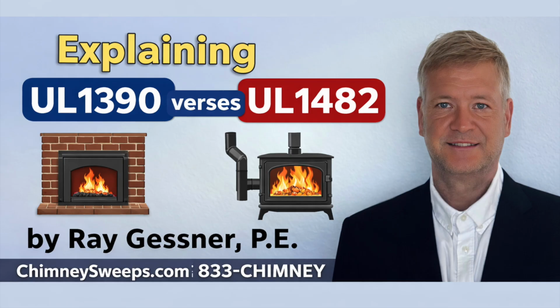Right. So if a manufacturer tests their new wood insert inside a brick fireplace, and it passes UL 1390 because the brick safely absorbed all the heat, and then a consumer takes that exact same certified insert and installs it into a factory-built metal fireplace surrounded by drywall and wood studs, the metal will conduct that intense secondary combustion heat directly into the framing of the house. The passing grade in brick becomes a guaranteed structural fire in metal. Wow, the safety simply doesn't transfer across materials. That makes complete sense.